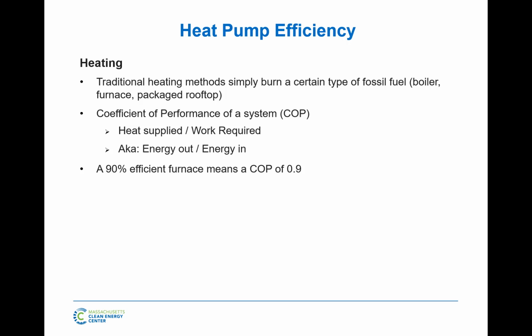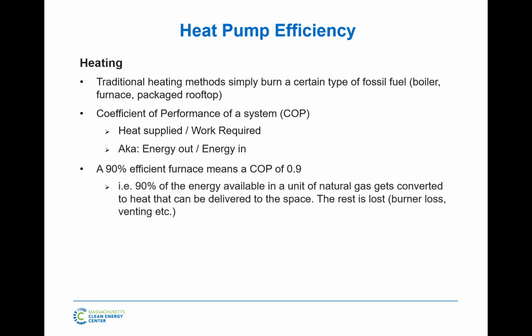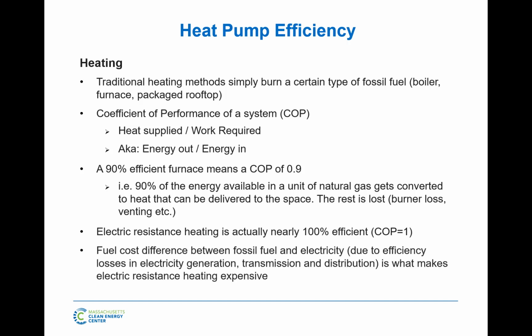Just so you know what that means, a 90% efficient furnace has a COP of 0.9. That means that for every unit of BTUs of heat from gas that you put into it, 90% of it goes out as heat. There are a few losses in there. An electric heater is 100% efficient. Every kilowatt of electricity you put in there goes out as heat. There's almost no losses. It's essentially virtually perfect. The problem is the fuel cost difference. Gas is cheap, electricity is expensive, generally, especially in comparison in our market.